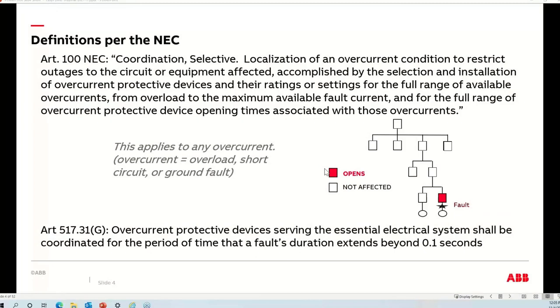There is a formal definition of selective coordination that appears in the code under Article 100. There's also another — not a formal definition — but a definition by usage in section 517.31, referring to 0.1-second coordination. The formal definition in the code — selective coordination — is universally accepted as meaning only the first device upstream of the fault would clear that fault, leaving the remainder of the system unaffected.